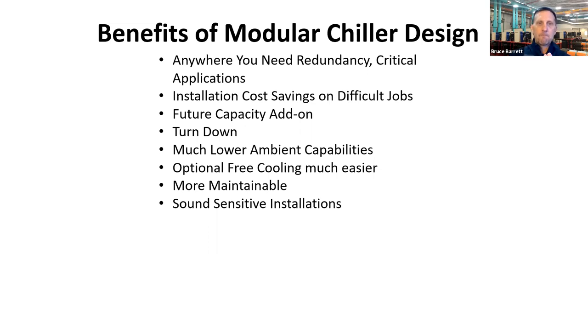Much lower ambient capabilities. Our modular chillers, because of our flooded head pressure control, minus 20 is our standard low ambient design. Optional free cooling, we've got a number of ways to do it. We could have individual free cools, or we can make them integral to the coil. More maintainable. If we've got a failure, failures happen, it's reality of life. If you've got that N plus one plus two capability, it doesn't become an emergency to maintain your load. And again, for sound sensitive applications, discharge attenuators, compressor wraps, a lot of creative ways we can do that.